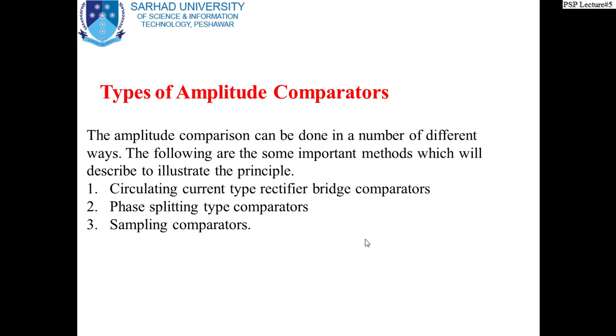Now, gentlemen, this diagram shows the rectifier bridge type amplitude comparator. The rectifier bridge type comparators are widely used for the realization of overcurrent and distance relay characteristics. The operating and restraining quantities are rectified and then applied to a slave relay or thyristor circuit as shown in figures A and B. The first figure shows a slave relay, which we will define later on, and we have already studied the thyristor circuit. So the first is of course with a slave relay, a sensitive polarized relay. This is basically a slave relay.